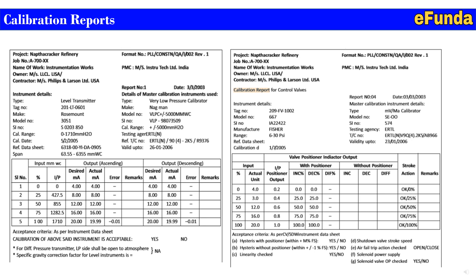The calibration record shows inputs in mm water column at five calibration points — 0%, 25%, 50%, 75%, and 100% — corresponding to input values of 0, 427.5, 855, 1282.5, and 1710, with desired output in 4 to 20 mA. Readings are checked in both ascending and descending conditions. Similarly, the control valve calibration report shows instrument details with input percentage, actual units, output of the I/P positioner, stroke action with and without positioner, and pass/fail status at each of the five calibration points.